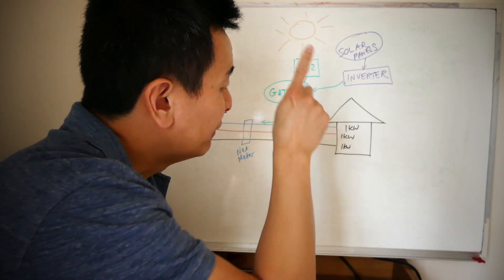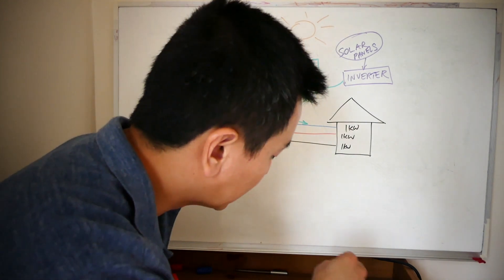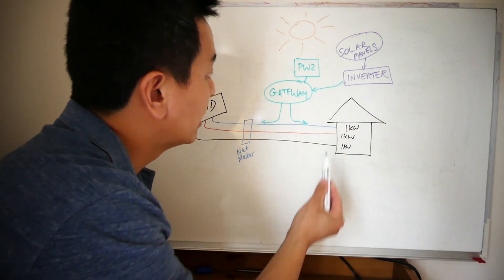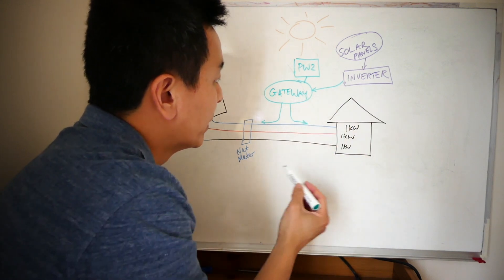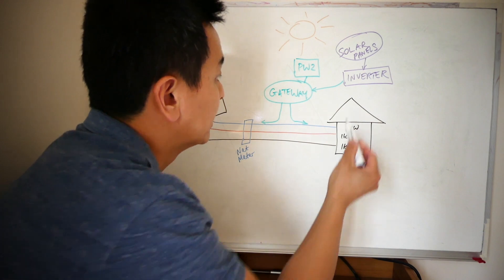If you have a three-phase inverter, now this is where it gets tricky for solar. If you have a three-phase inverter, you can only send one phase from the inverter to the gateway, and the other two phases have to go to the house like this.